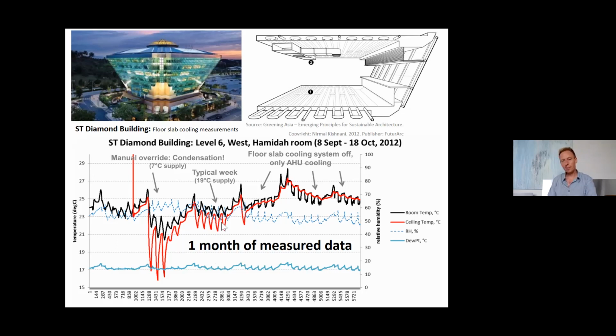So therefore, no condensation will happen, except when you get a new building facility team into the building, which happened the week before, and where they decided for some reason to manually override how the system operates. So instead of supplying 18-degree water into the slab, they just took normal 7-degree chilled water, and therefore the ceiling temperatures dropped a lot, as you can see here, and dropped below the dew point, and therefore you basically had droplets forming, and it was sort of raining in the offices for these 3 days. Then they panicked, went back to the setting before, and then maybe more complaints, I don't know, from whatever, and then they switched off the system for a couple of weeks.